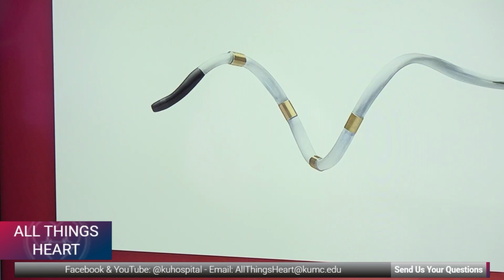So there are these electrodes on that, those gold bands. Why do you need 4? Because the renal arteries are quite long and there are multiple branches, and the first generation actually only had 1 electrode. So the procedure took a long time. There was a lot of manipulation. So now we can put 4 ablation points at one time.